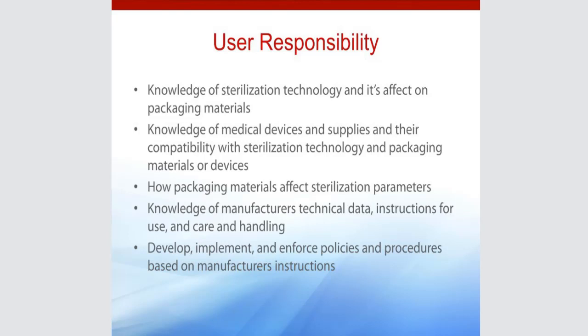We want to make sure that these supplies are compatible with the type of sterilization technology that we each have in our offices. Now in dentistry, we're pretty lucky because the vast majority of offices use steam sterilization in one form or another. They're either going to use the very traditional gravity displacement sterilizer, or they may be using a dynamic air, which would be like a pre-vac or a Class B sterilizer, or the steam flush pressure pulse, SFPP. And you want to make sure that the products that you're using are going to be compatible with the equipment that they're being used in.